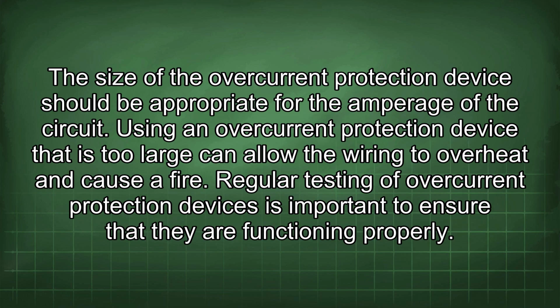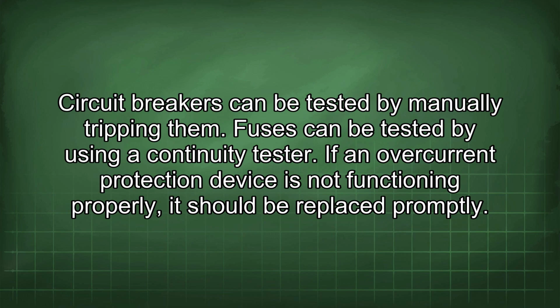Regular testing of overcurrent protection devices is important to ensure that they are functioning properly. Circuit breakers can be tested by manually tripping them. Fuses can be tested by using a continuity tester. If an overcurrent protection device is not functioning properly, it should be replaced promptly.